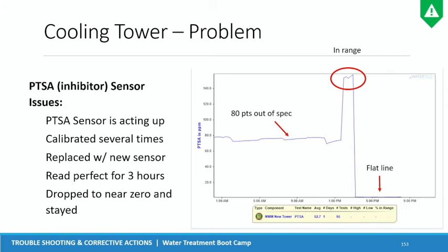sensor on this graph, but you can actually see if the level of the chemical is going down. If the level of the chemical is going down, you can say, okay, chemistry is going out of the tank. Now, I don't know if it's going in the system or just falling out, but it's happening. So at that point, you bring in the operator and you say, okay, can you check what's going on? Make sure you look at the wiring, chemicals in the system, flow is going through, the chemicals actually making into the system. It's a faulty sensor, so you get that replaced again.